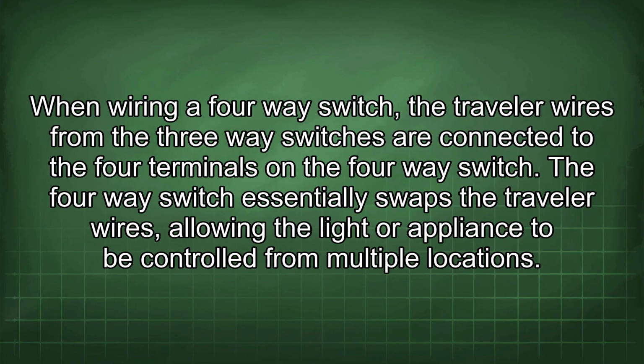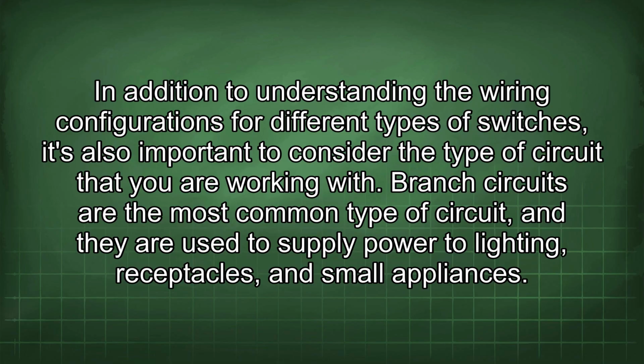When wiring a four-way switch, the traveler wires from the three-way switches are connected to the four terminals on the four-way switch. The four-way switch essentially swaps the traveler wires, allowing the light or appliance to be controlled from multiple locations. In addition to understanding the wiring configurations for different types of switches, it's also important to consider the type of circuit that you are working with.